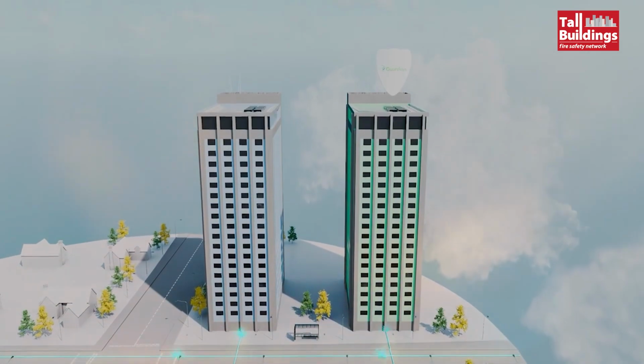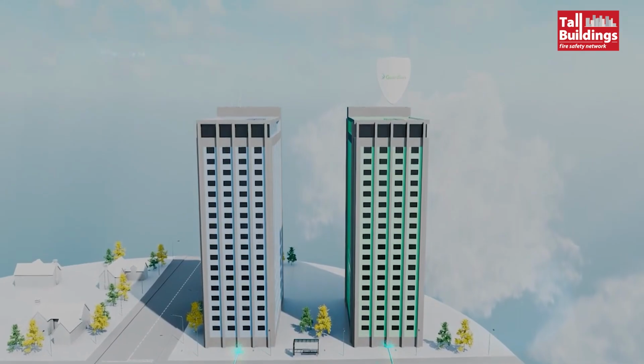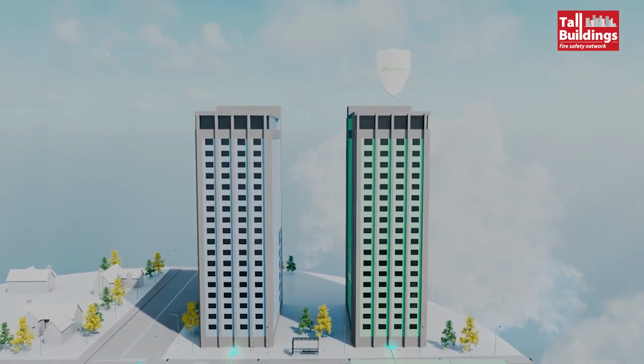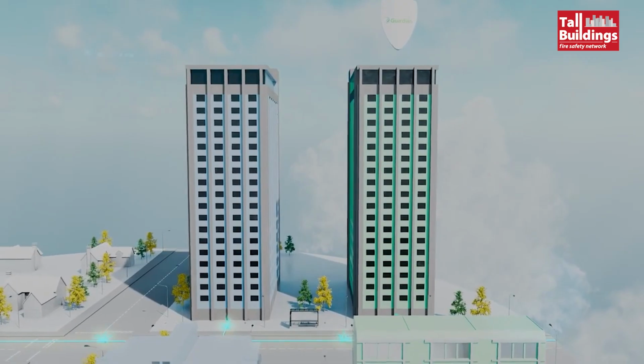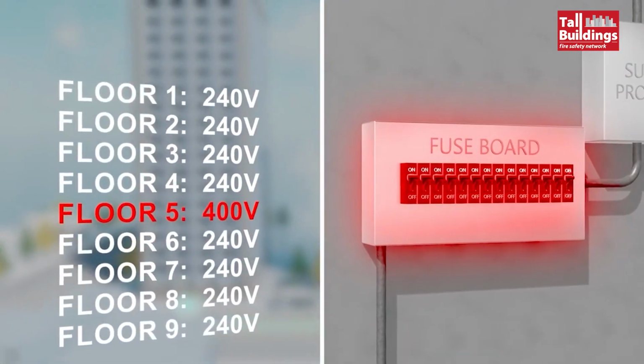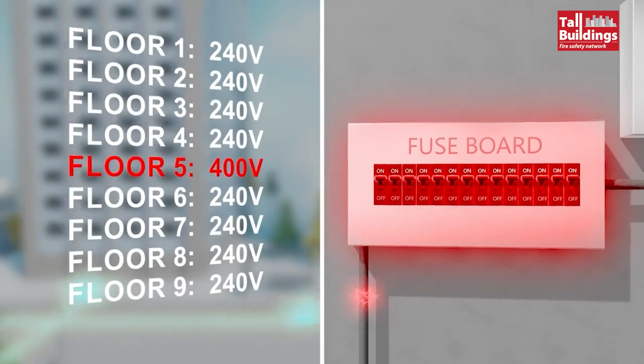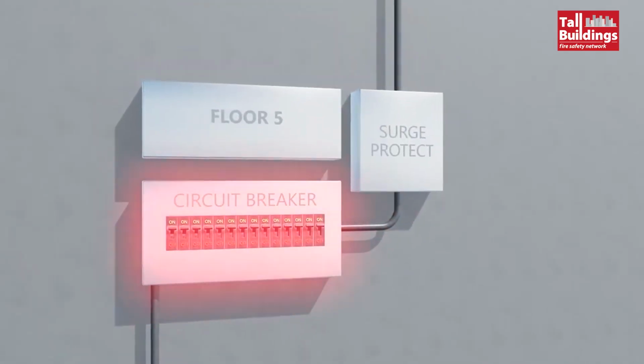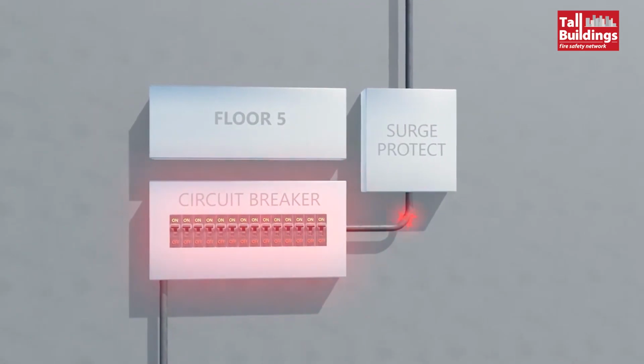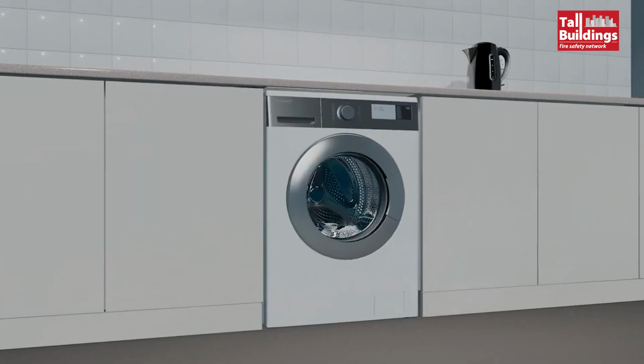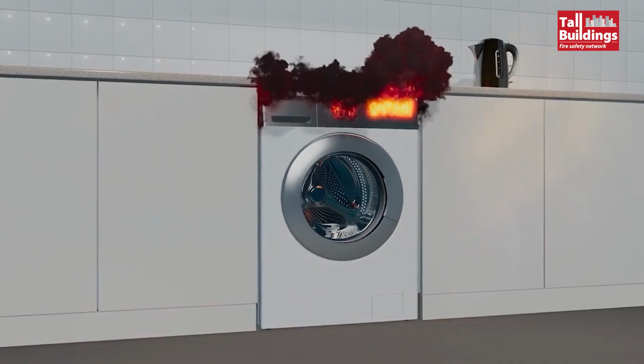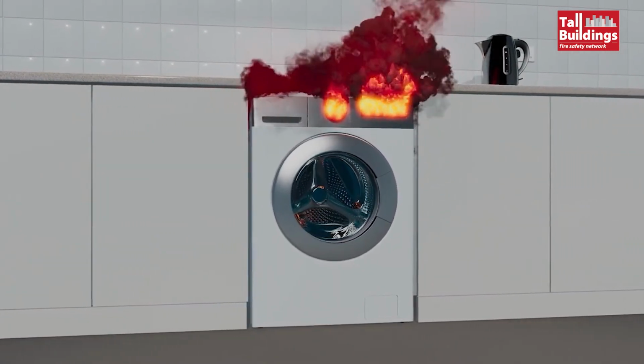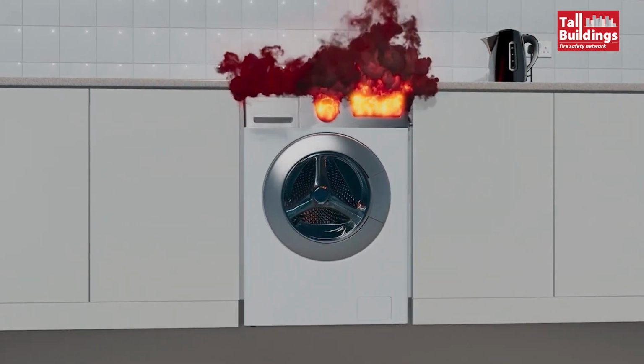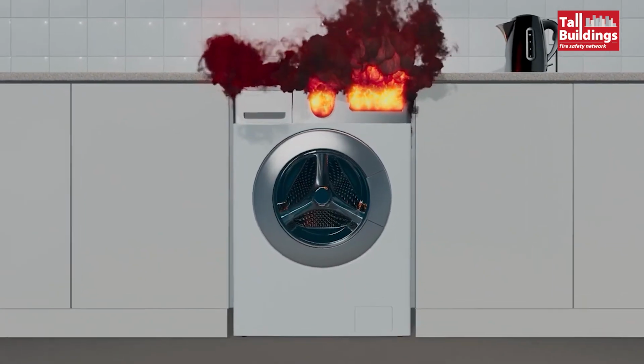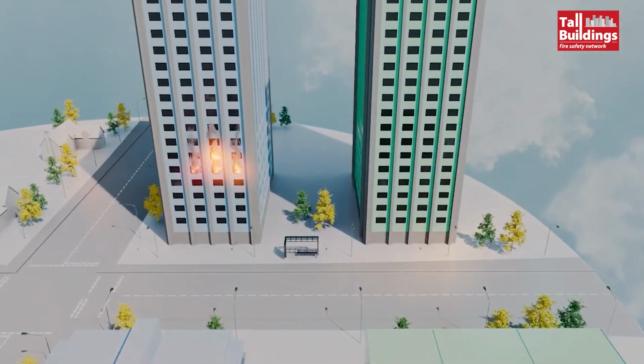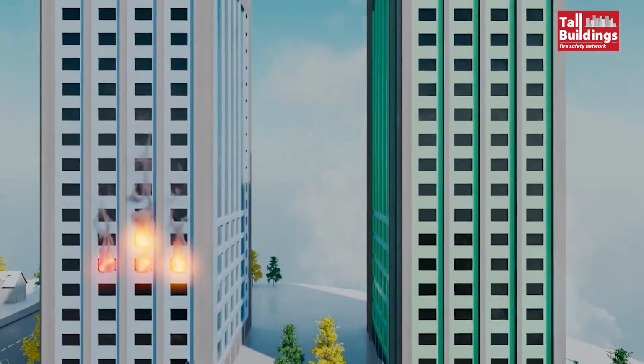In this instance, the incoming supply is undamaged and enters both apartment blocks. However, danger is lurking. The neutral to the fuse board that supplies floor 5 has broken loose. High voltages are now present in the apartment supplied by this fuse board, and a serious incident is about to occur. While other apartments supplied from different fuse boards within the building may not be aware of any electrical fault, the high voltages would damage electrical appliances and could cause fire to break out. The fire alarm electronics could also be damaged by high voltages and may not be able to alert the building users, which now becomes a danger to all floors and unsuspecting homeowners.